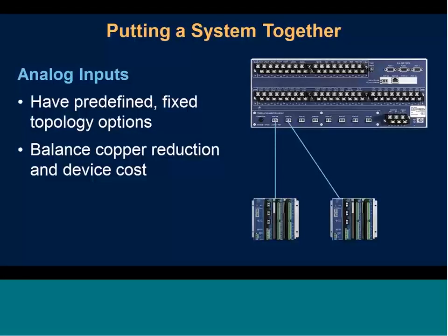So the question is, if there's no network engineering and all of that, how does my relay map all of my currents and voltages? Well, you can see on the right a picture of the back of what a TiDL relay looks like. What we did is replace the CT and PT connections with these fiber optic ports—EtherCAT ports—and there's a total of 8, so we can communicate with up to 8 Axion units. We don't always communicate with 8, but essentially how we plug in our Axions to those 8 ports tells our relay how to map the analog values.